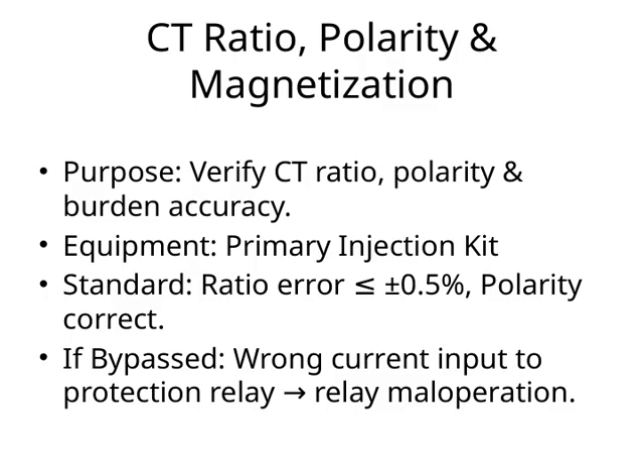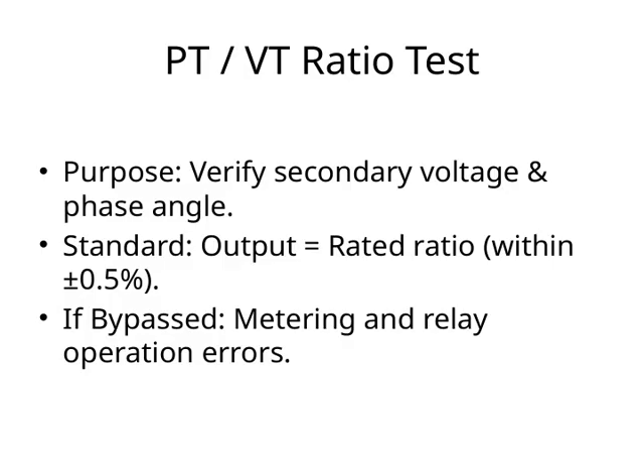the electrical network. Let's take a closer look at the PT/VT ratio test. The main purpose of this test is to verify the secondary voltage and phase angle. Ensuring these are correct is crucial for the accurate operation of protective devices and metering systems. The standard we aim for is that the output should match the rated ratio, with a tolerance within plus or minus 0.5%. This small margin helps us confirm that the transformer is performing accurately and reliably.